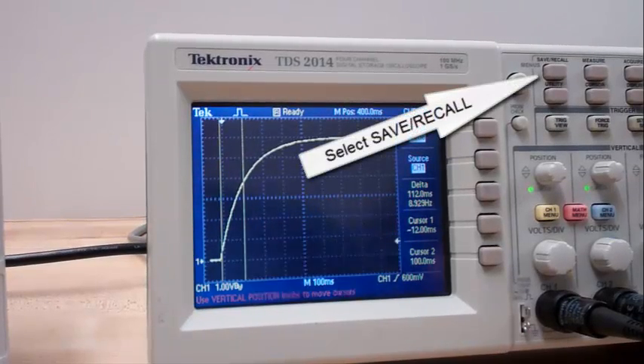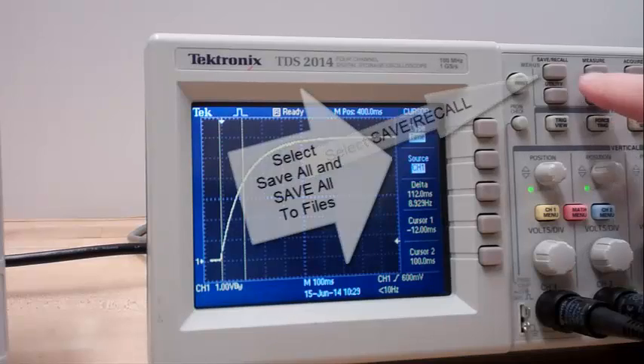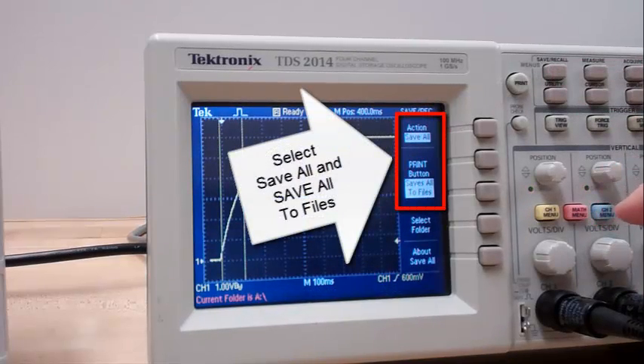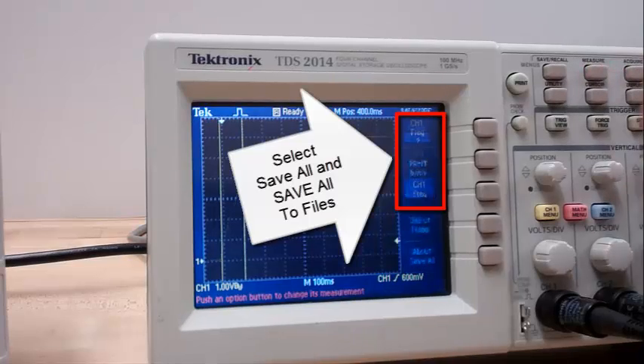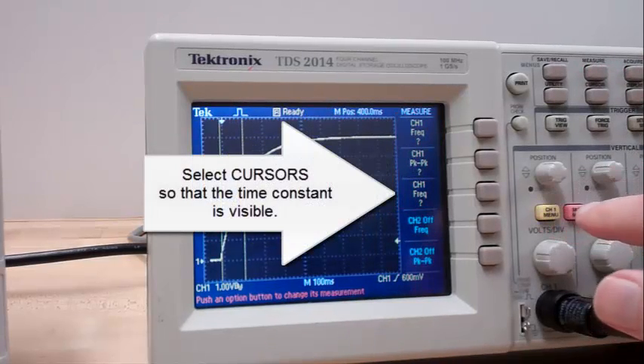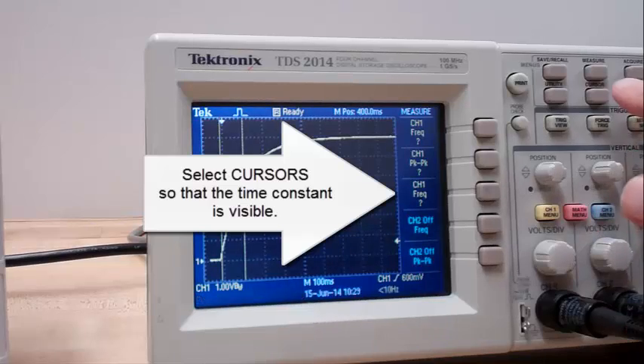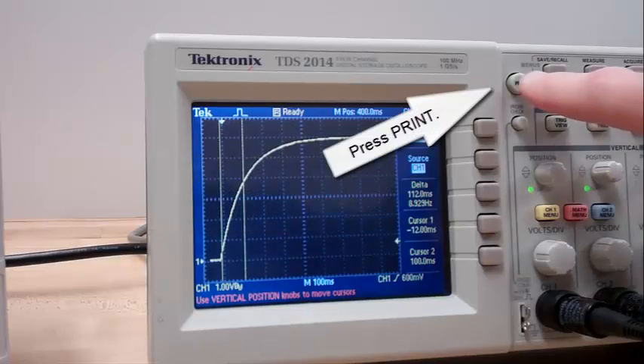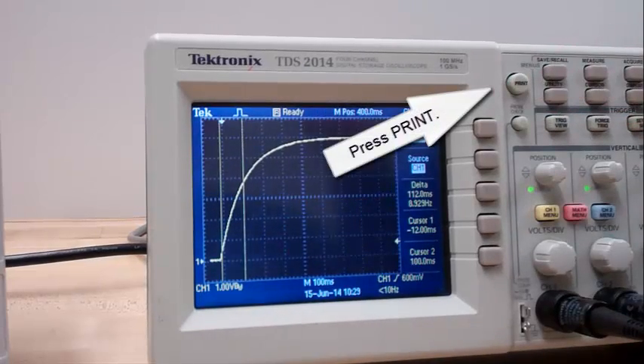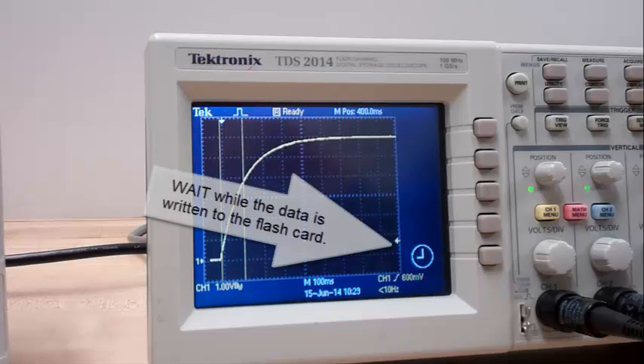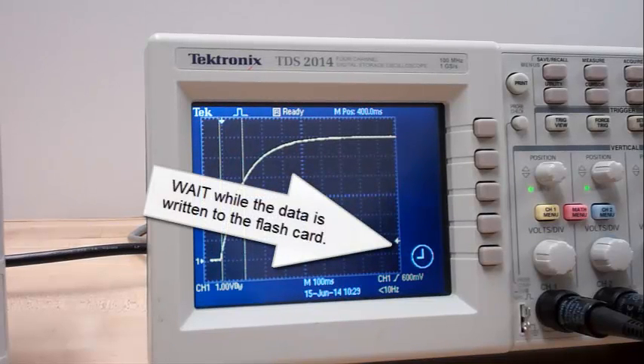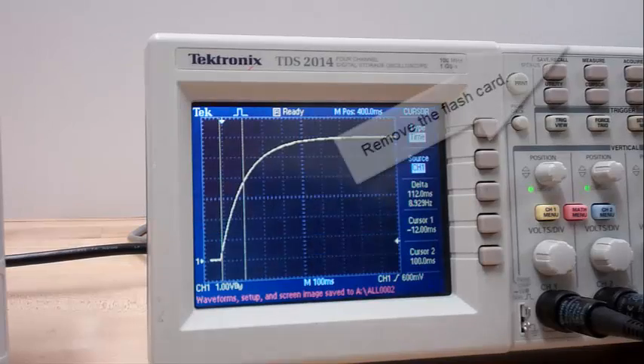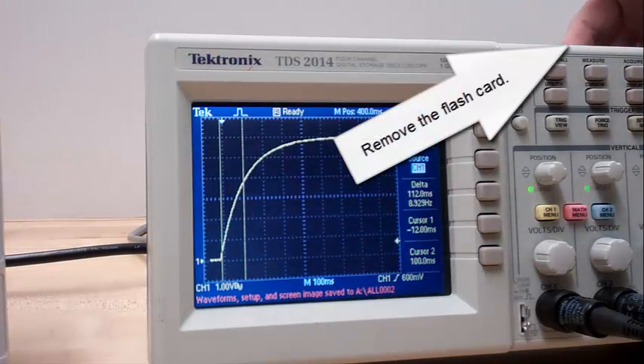Select save, recall, select save all, save all to files. Then select cursor so that the time constant is visible. Press print. Wait while the data is written to the flash card. Remove the flash card.